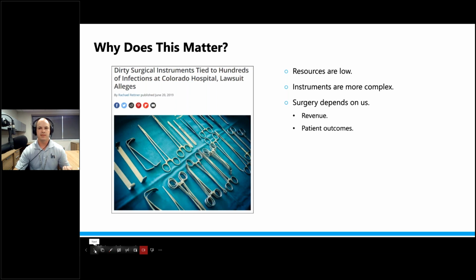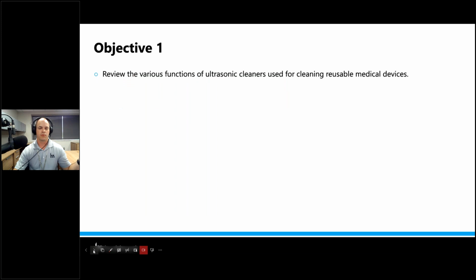Those cracks and crevices are very common with surgical instruments. Now, key components of producing that cavitation function are ultrasonic generators, like you see here in the middle of the screen. That's just an example of one generator. There are many different looks of the generators, but it's a good idea in your department to get an understanding of the ultrasonic cleaner that you have. Where's the generator? Does it have an on-off switch? That kind of thing. And then the generator feeds the energy to the transducers, which you see on the right side of the screen.